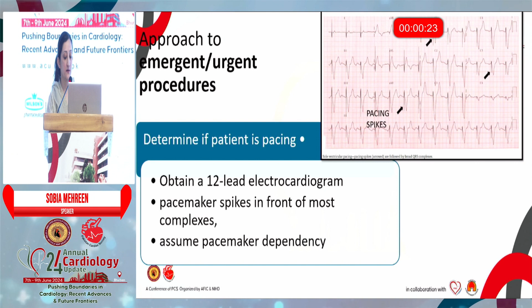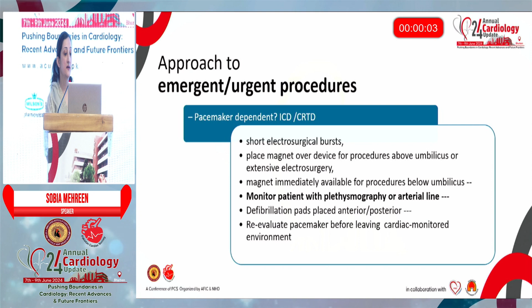In case the patient is pacing dependent or has a defibrillator and is undergoing emergency surgery, we need to follow these steps: short electrosurgical bursts, magnet placement over the device for procedures above the umbilicus, magnet availability for procedures below the umbilicus, monitoring of the patient with an arterial line and plethysmography apart from telemetric recording, placement of defibrillation pads in AP position, and re-evaluation of the device before the patient leaves the surgical environment.